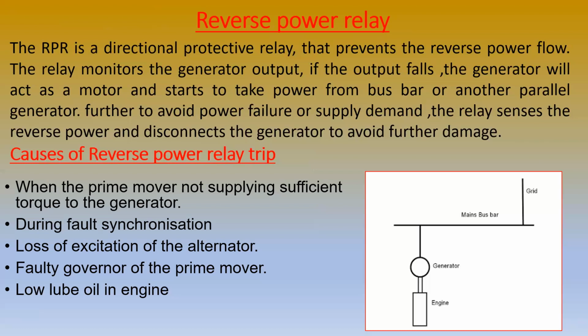And the torque produced by the generator will be less when the mechanical torque is less. So when the main torque is less than the losses, automatically the generator cannot provide the power. It starts to take power from the bus bar, so it will act like a motor. Motoring action will start and it will consume power from the main bus bar. So this will add to the high demand for power supply and the whole system may go into blackout condition.